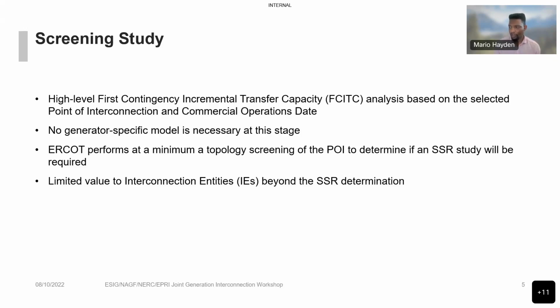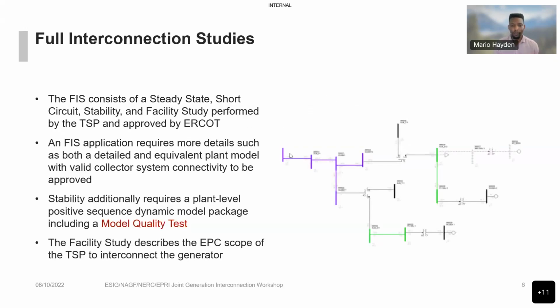Beyond the SSR determination, there's limited value in the screening study, which leads us to the bulk of the interconnection process: the full interconnection studies, or FIS. The FIS consists of steady state, short circuit, stability, and facility studies, which is pretty common across the country—the naming may differ, but the content is pretty uniform. The FIS application requires a more detailed suite of inputs, including a detailed and equivalent plant model with valid collector system connectivity, in order to be approved to move on to a kickoff call, steady state study, and beyond. The stability study additionally requires a plant-level positive sequence dynamic model package, including a model quality test, which I'll dive into later. The facility study instructs the EPC scope of the TSP in terms of design, procurement, long lead items, and construction scope, so there's an actual physical facility for the generator to connect to.